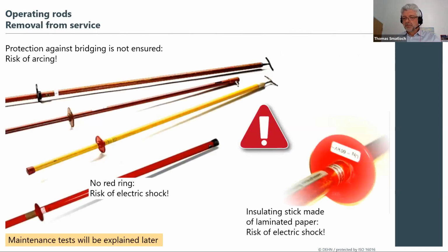Here we have a picture of some old instruments you might still find today in older installations. And those are elements which are not made after the latest standard. Here we have different sources of faults, as we can see. You can see on top of it, we have metallic parts. So there is always a danger that this metal part could bridge some elements within the switchgear cabinet and create arc faults. So this is not safe, of course.